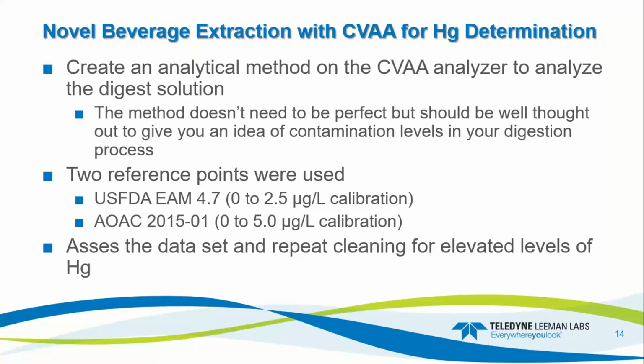So we have the vessels, the vessel caps, the volumetric flasks, funnels, and the test tubes that are going to be loaded onto the instrument. So there are a lot of points for contamination, and we need to look at all those points. So set up a method on the analyzer. It doesn't have to be perfect, but it has to be well thought out so you can get an idea of the contamination levels within your digestion process.